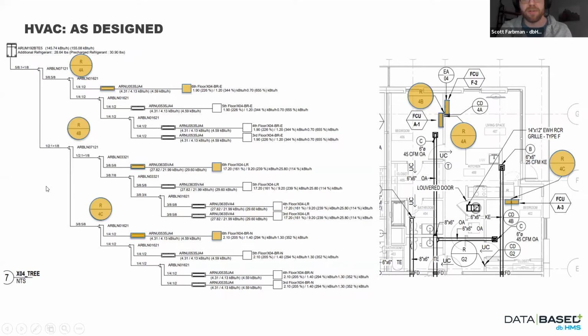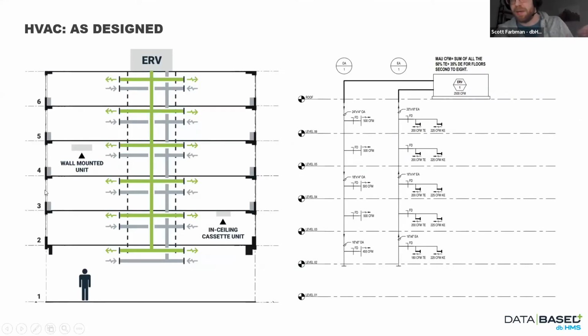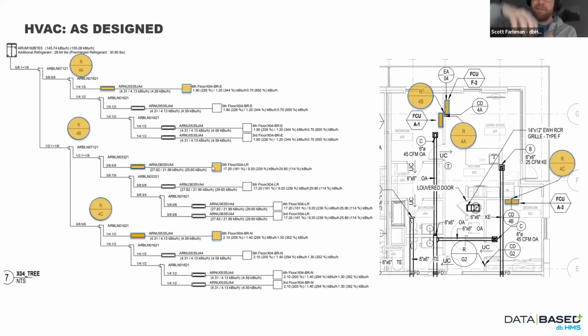There's a couple other ways to do this. So we've seen it be, let's go back for a second. So we went vertical stack here. We assessed very early, there's a heat recovery option to VRF. So there's a branch box and everything comes back, and you can trade off efficiencies in your indoor loop. If you have some places calling for heat, some places calling for cooling at the same time, you could reap some of that in the loop efficiency and design. In order to do that, we would have had to do more of a horizontal split. So maybe we have one outdoor unit per floor, and maybe the south side is calling for cooling and the north side is calling for heating. East and west changes throughout the day. That's something that we could do, but again, we didn't really find energy savings at a heat recovery level.